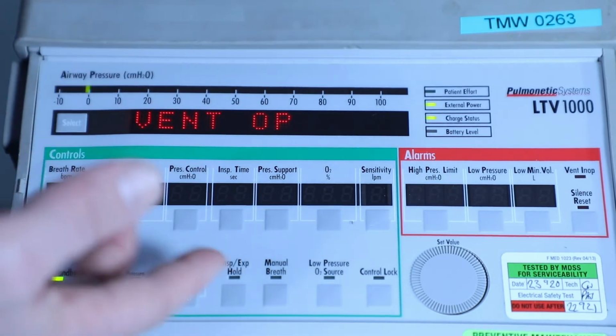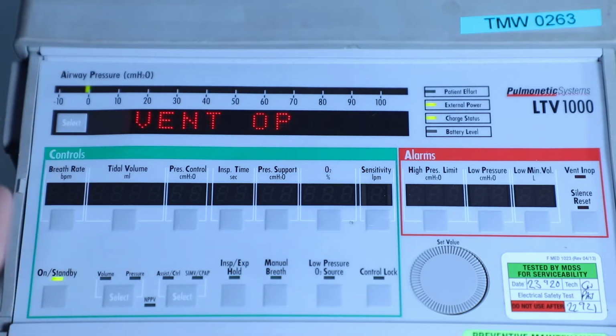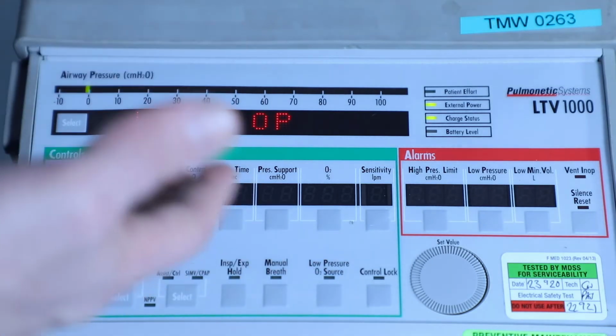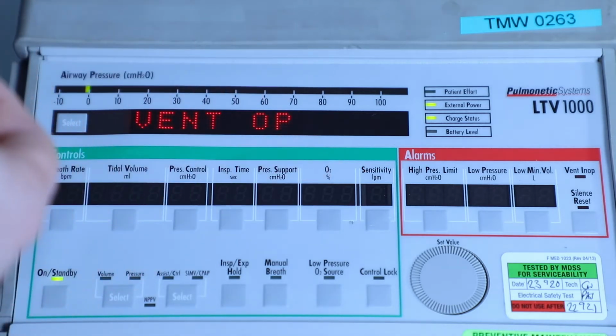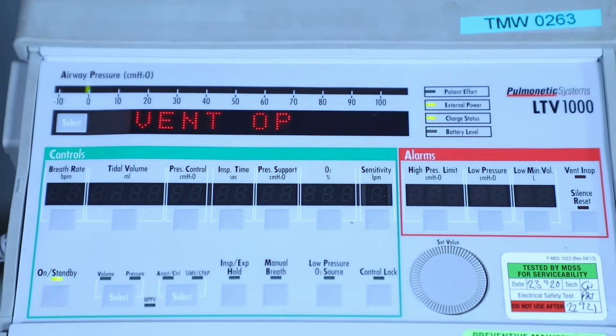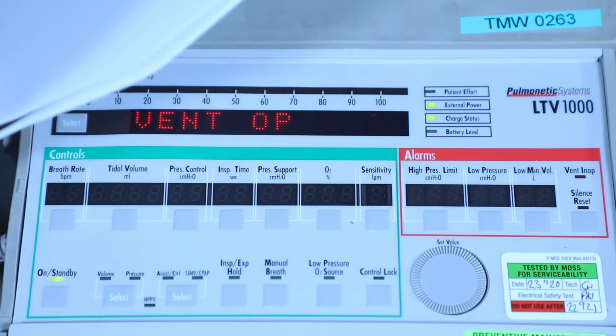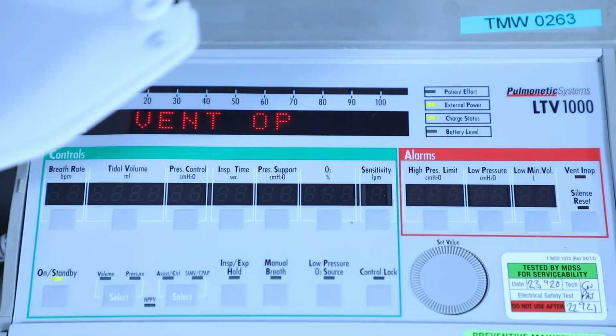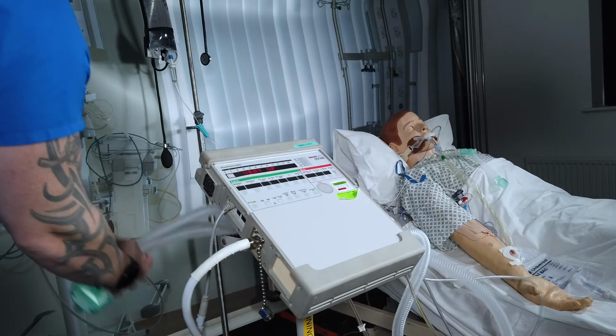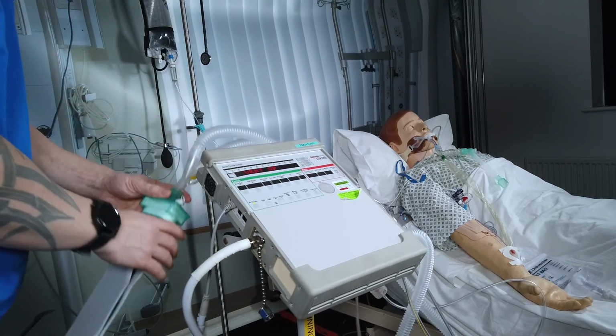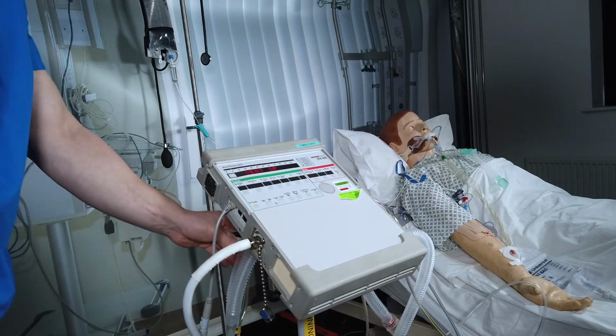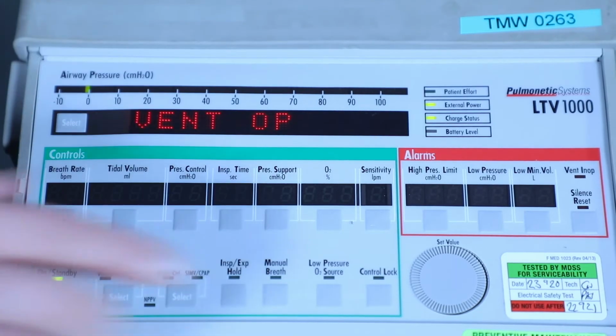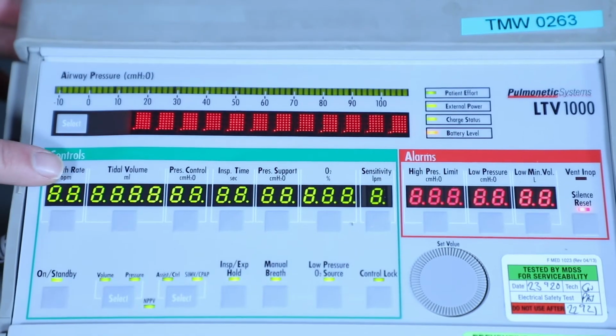Next, we want to check the function of the ventilator. So we need to attach up the test lung to simulate attached to a patient, and then we'll run through some real-time data to ensure that the ventilator is operating accordingly. So for this we need the test lung, and we also need the 12 amp hour battery, which I've got beside me now, so that we can test the device operating on an external power source. Connect the test lung up to the end of the patient circuit. And then we want to press the control unlock, which takes us into a ventilation mode.